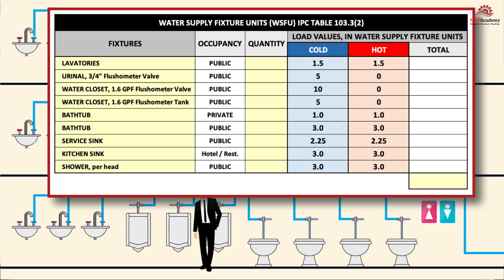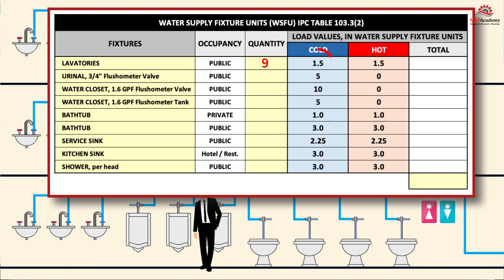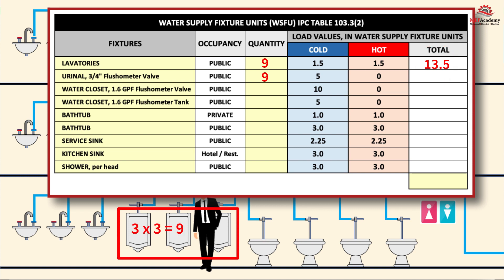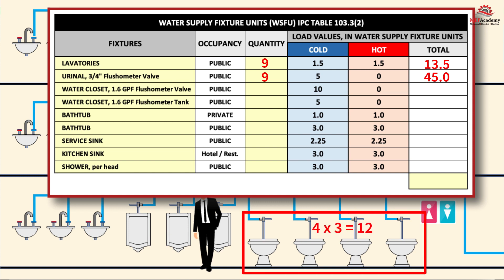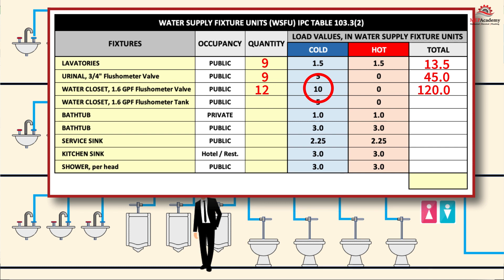Multiply the WSFU of each fixture by the number of fixtures of that type to get the total WSFUs for each fixture type. For example, there are three lavatories per floor times three floors, equaling 9 lavatories total; at 1.5 WSFU each, that gives 13.5 fixture units. There are 9 urinals at 5 fixture units each, totaling 45. There are 4 water closets per floor times 3 floors for 12 water closets; at 10 WSFU each, that equals 120 fixture units.